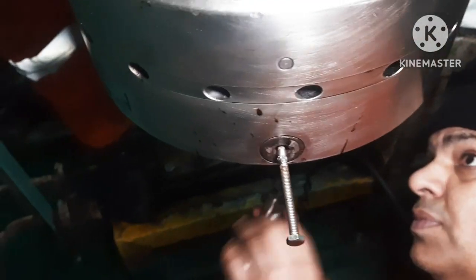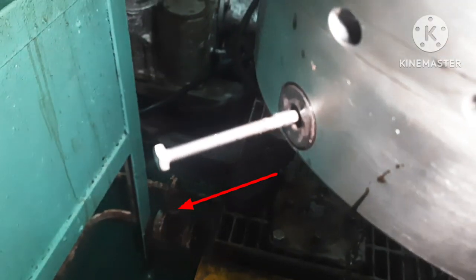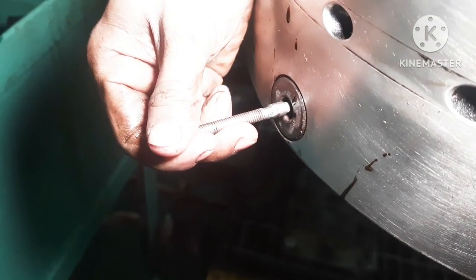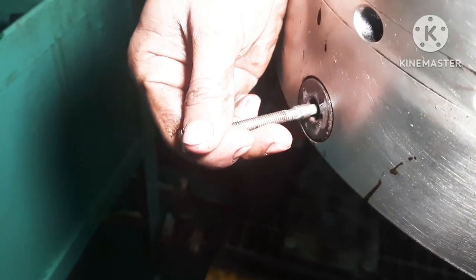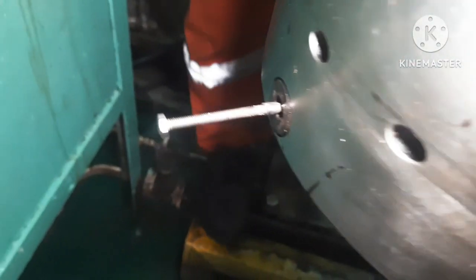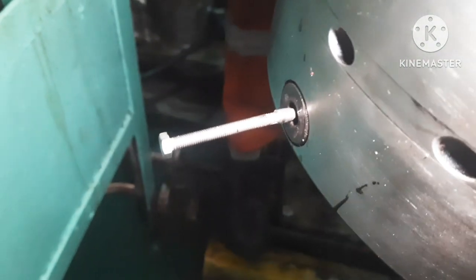After fixing the bolt, we should lift the bolt assembly by chain block, then pull this bolt outward as far as possible. Then apply the compressed air as described before. You will see the bolt move inward. If the bolt moves inward, that means the pilot valve is okay. If the bolt moves to the outer side, then the pilot valve needs to be overhauled again.